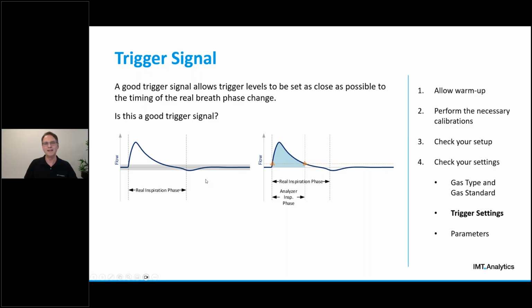However, there is no way here to set a sufficient trigger for the end of the inspiration phase. The flow signal is just too flat here in this area, and the changes of the signal are within the zone we can't properly trigger without risking false triggering. So if we would set the end trigger to the same level as our start trigger, close as possible to the gray area on a falling edge, we will have a huge mismatch between the real breath phase and the breath phase detected by our analyzer. So this is not what we want. So again, this is not a good trigger signal.